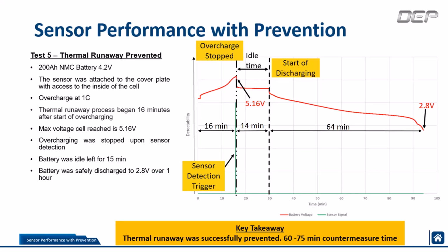Now, in this last test, we actually had a 200 amp hour NMC battery, and instead of doing a repeat or pushing this into thermal runaway, we decided to prevent it. So we took our chance. We overcharged the cell at 1C. 16 minutes into the test, you'll see the voltage was increasing, and it suddenly stopped right when our sensor sent out a detection signal. So this digital signal is what our sensor detected. Once we received the signal, we stopped the overcharging.